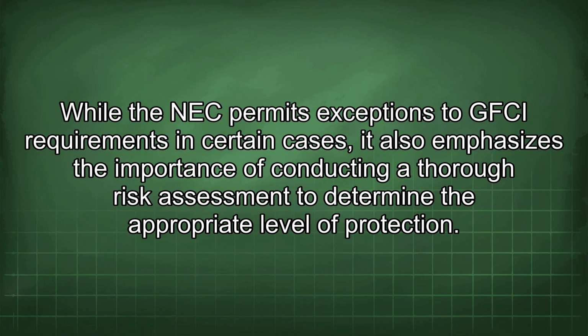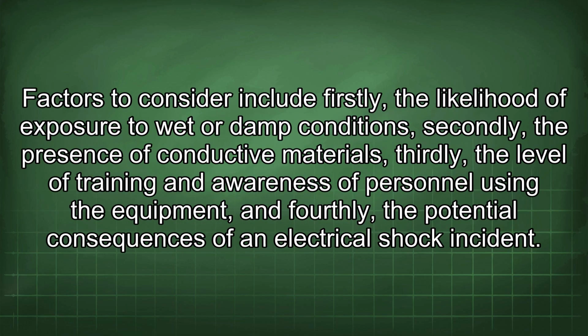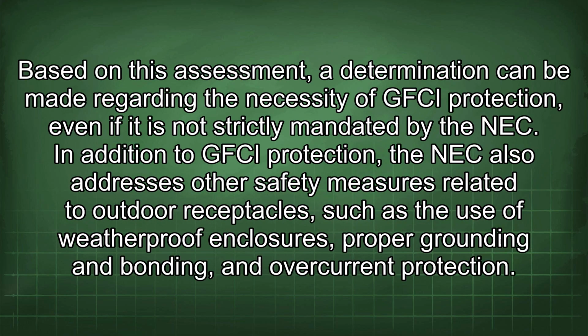While the NEC permits exceptions to GFCI requirements in certain cases, it also emphasizes the importance of conducting a thorough risk assessment to determine the appropriate level of protection. Factors to consider include, firstly, the likelihood of exposure to wet or damp conditions, secondly, the presence of conductive materials, thirdly, the level of training and awareness of personnel using the equipment, and fourthly, the potential consequences of an electrical shock incident. Based on this assessment, a determination can be made regarding the necessity of GFCI protection, even if it is not strictly mandated by the NEC.